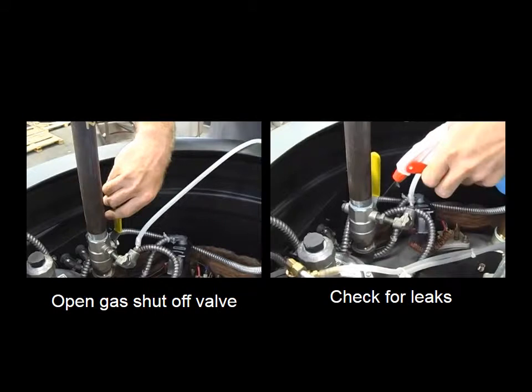Open the manual gas shutoff valve at the burner and check the gas train for leaks using an appropriate bubble detection solution. If any bubbles are detected, close the manual gas valve and tighten the connection. Then reopen the manual gas valve and recheck to ensure there are no leaks. Natural gas is now supplied to the unit.